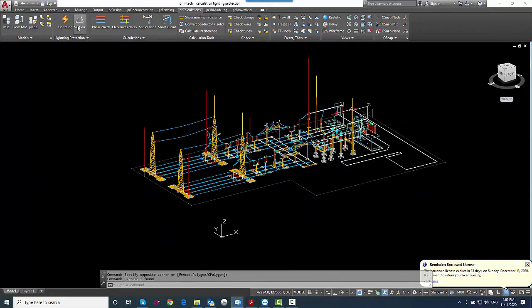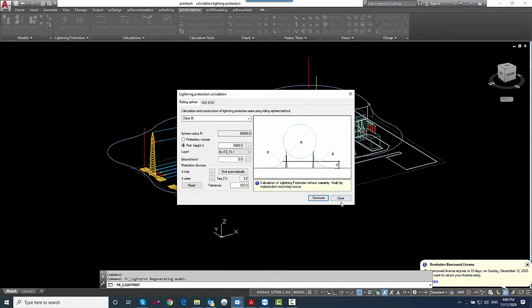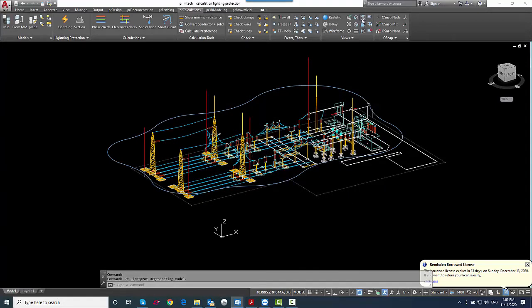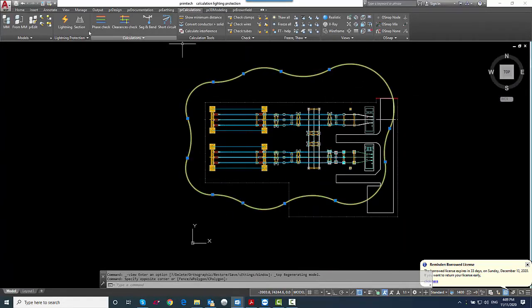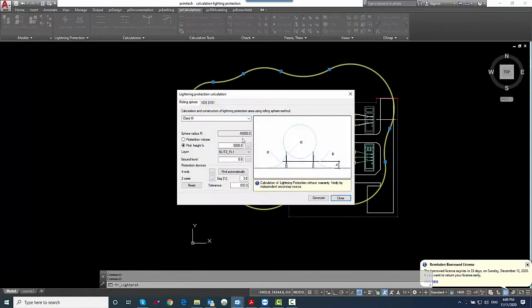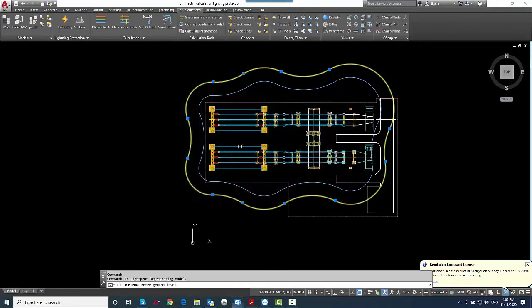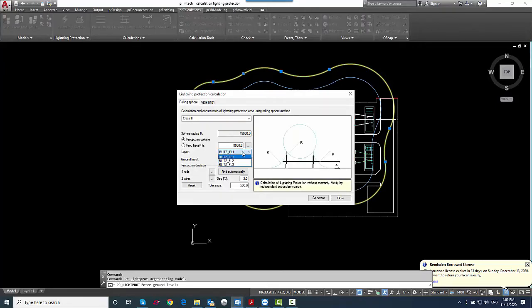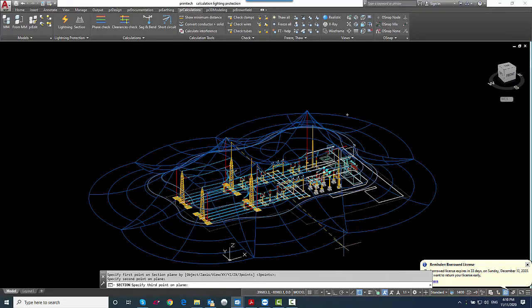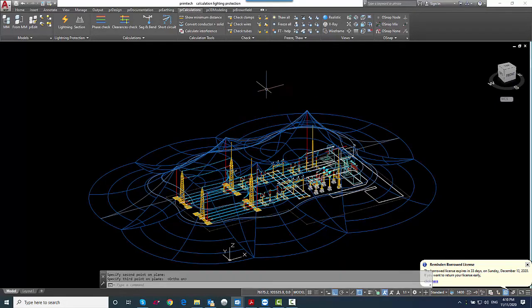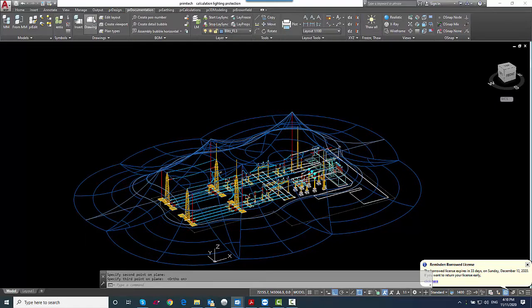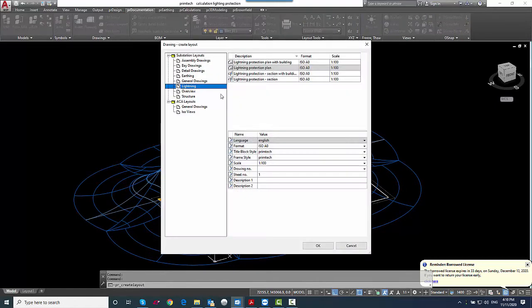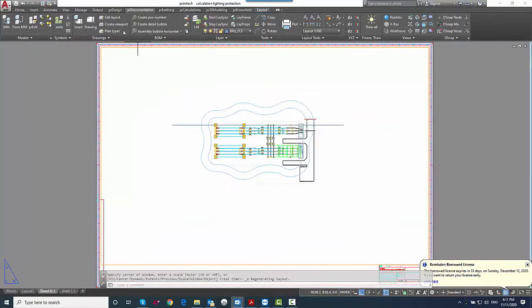Another option you have is that you not work with a protection volume. So you can also create basically 2D lines on a specific height of the protection volume of your substation and represent the protected area on that height in, for example, a top view. Of course, you can also create a section of our protected volume, of our protected area, and can put that on a lightning protection plan.